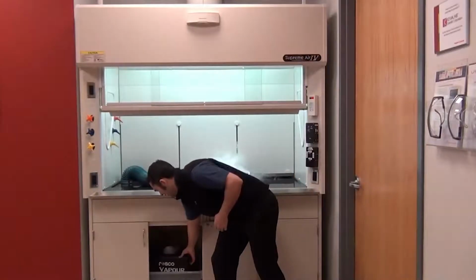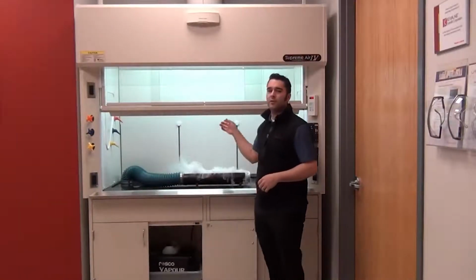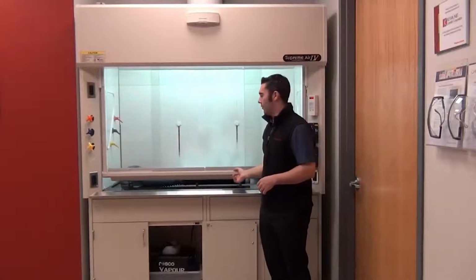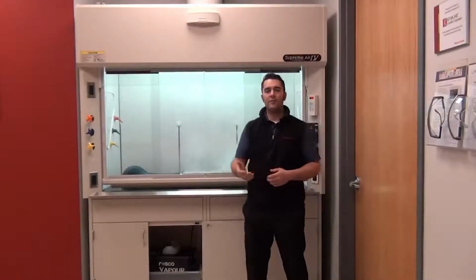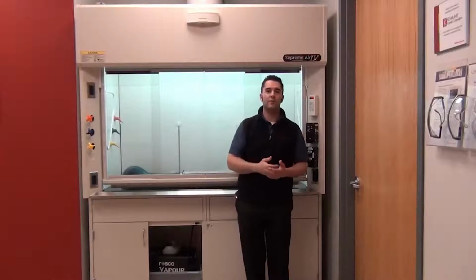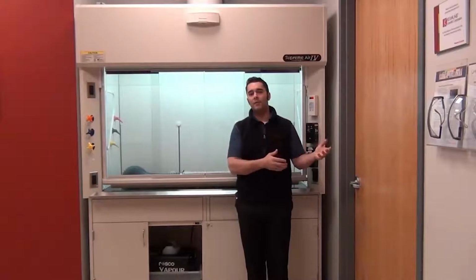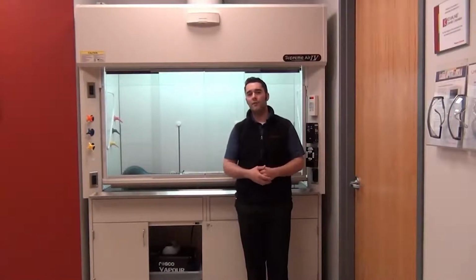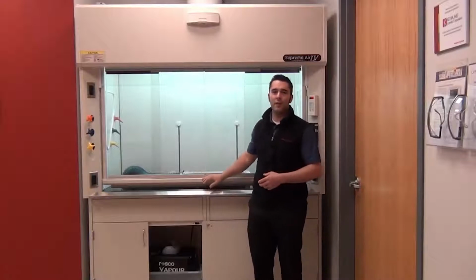The second way that the Phoenix Controls products save money is through a function we call Hibernation Mode. Now if you're thinking about wet chemistry applications, again in pharmaceuticals or places like that, typically the fume hoods are assumed to be running 24 hours a day, 365 days a year because they're always doing some kind of testing. But when you get into applications where you might have a compounding pharmacy in a hospital, or you might have a teaching university where you have a lot of fume hoods inside of a room that might only get used 3 months out of the year, I don't need to run this fume hood at its full value all the time.